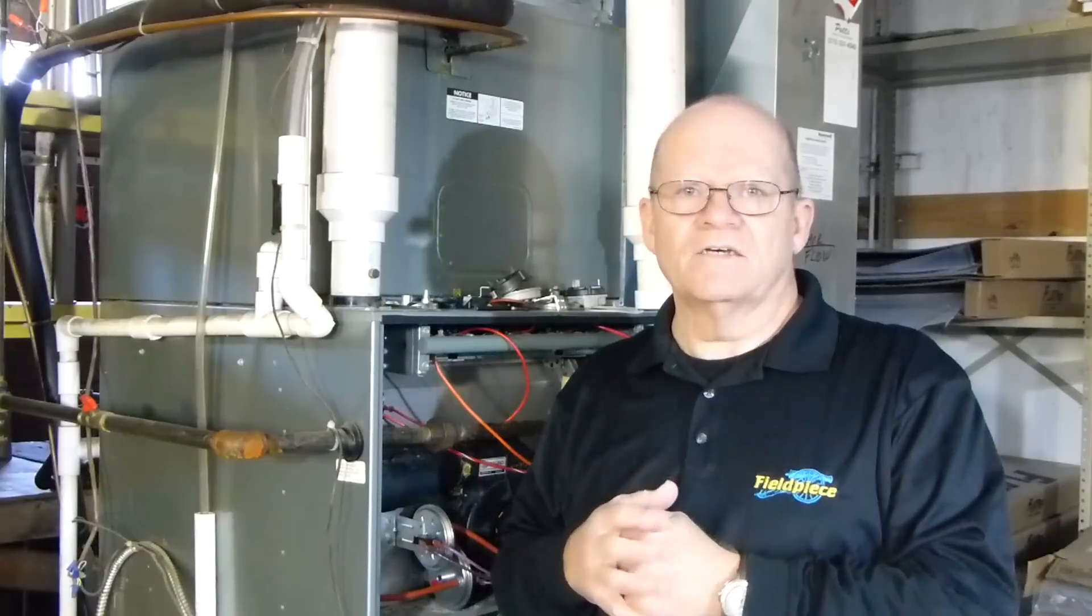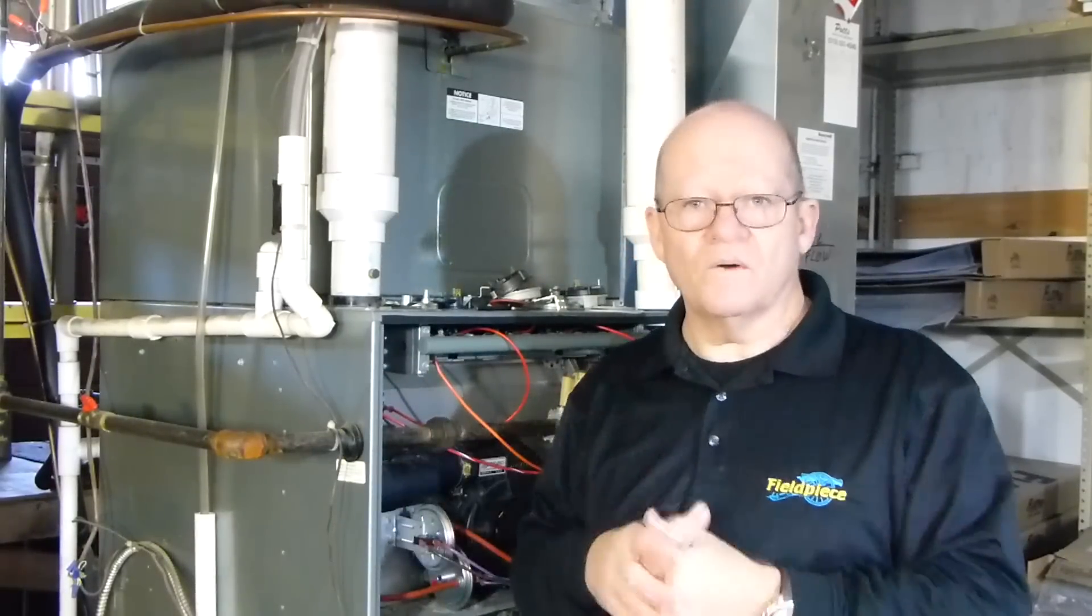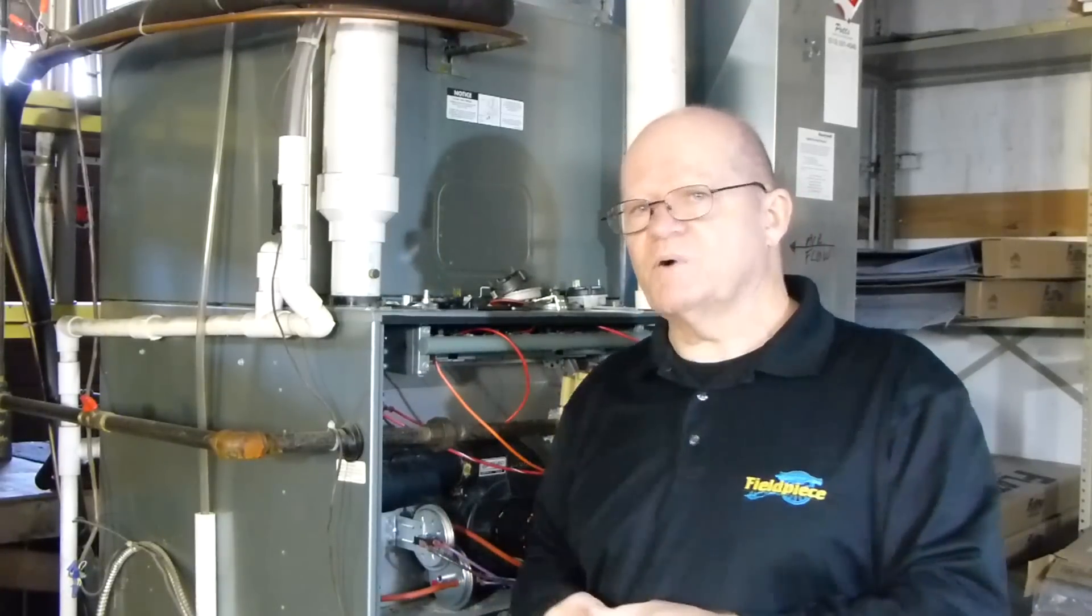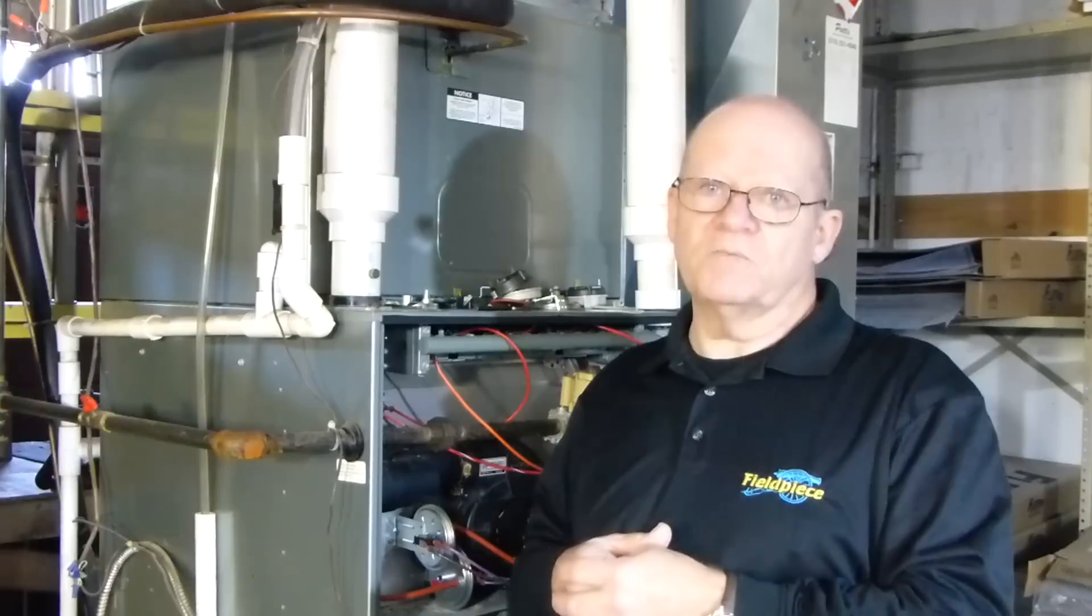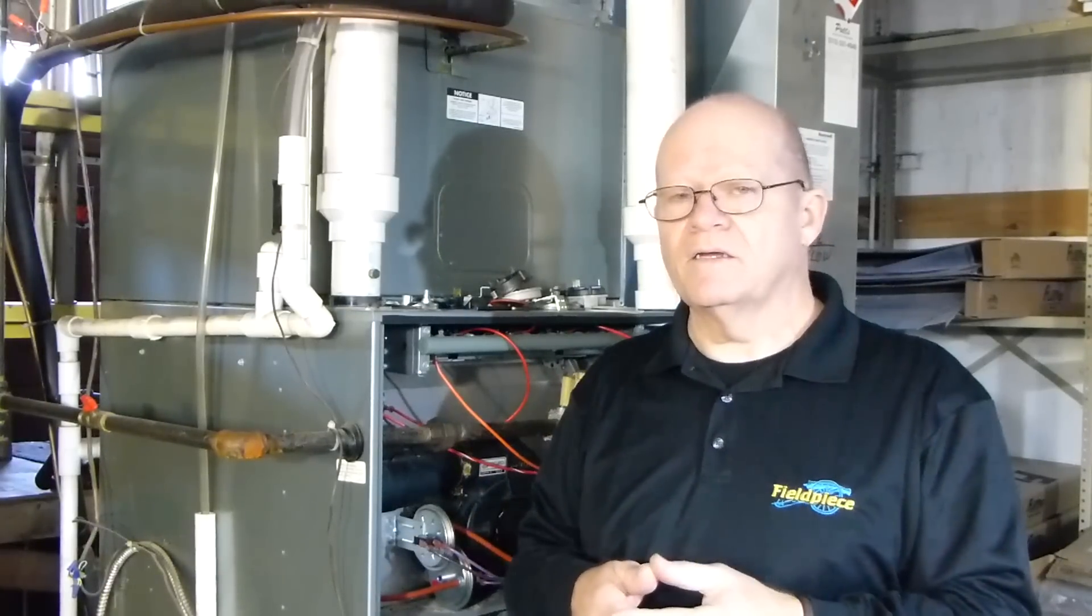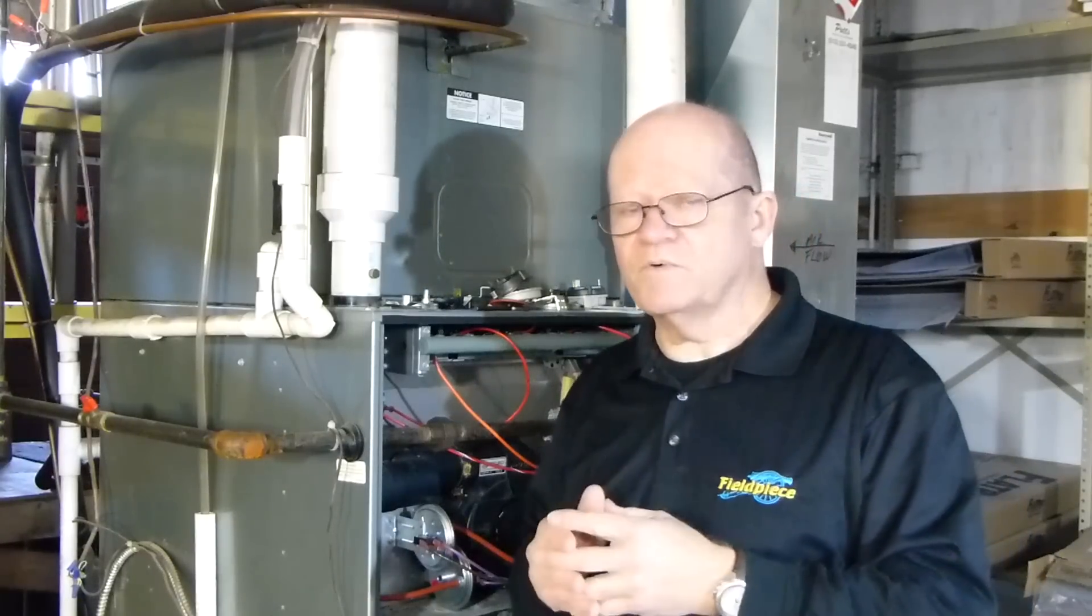It's going to act like it's a 0.30 or 0.40—even lower. So that being the case, if your heat exchanger is partially blocked, or your flue is partially blocked or even blocked, your furnace is going to continue to run under those conditions. So I highly recommend you check that bleed port as well.